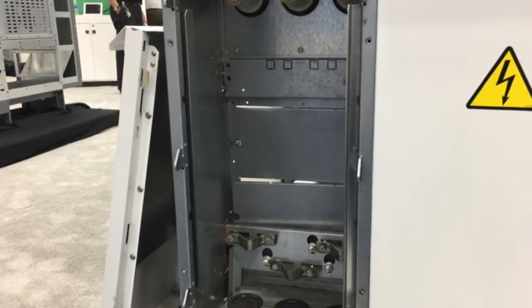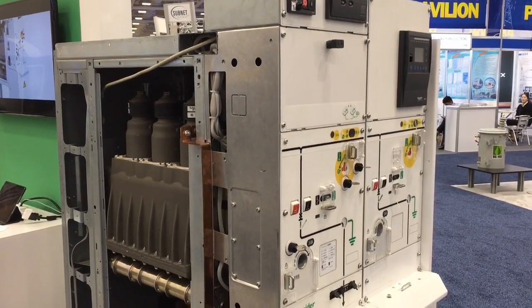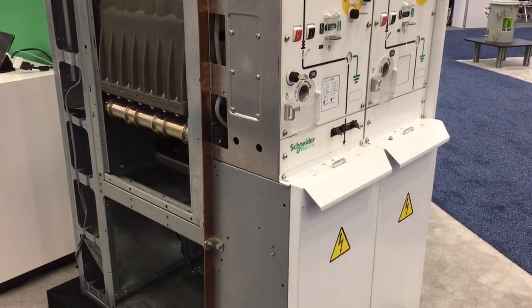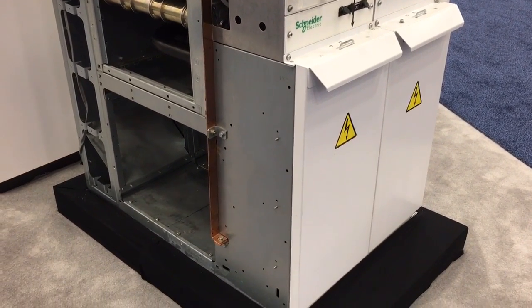The grounded shielding negates the radiation of electrical and magnetic fields in the space between the current carrying portions of the switchgear. This serves to increase the switchgear life expectancy by greatly reducing negative effects on the insulation and helping to prevent internal current crossover.